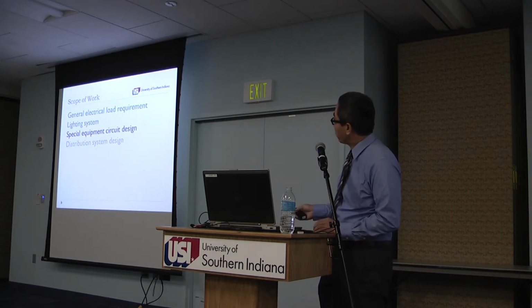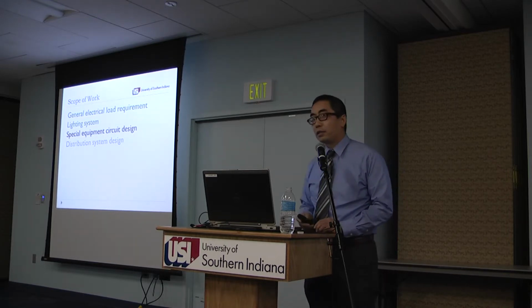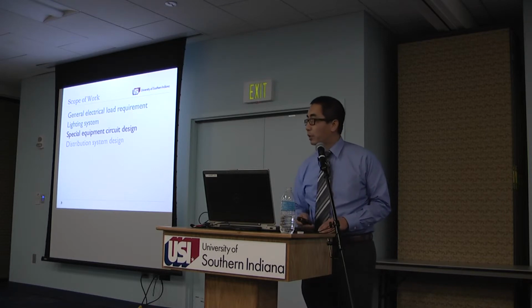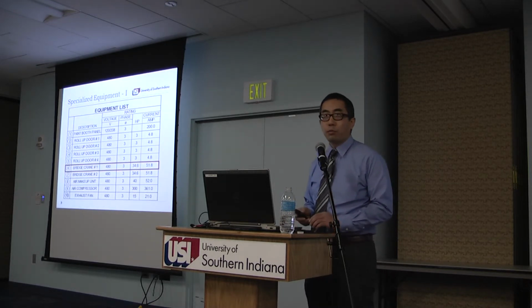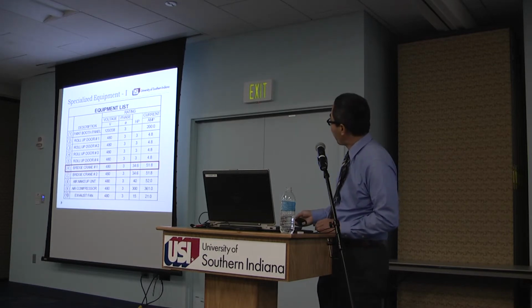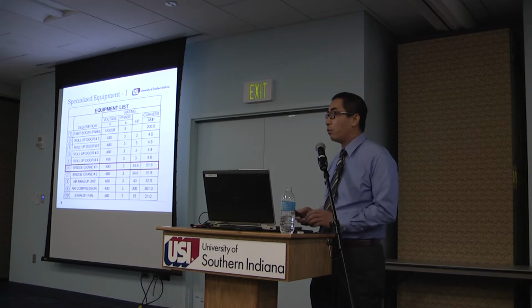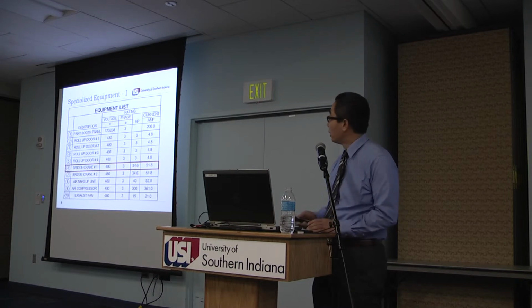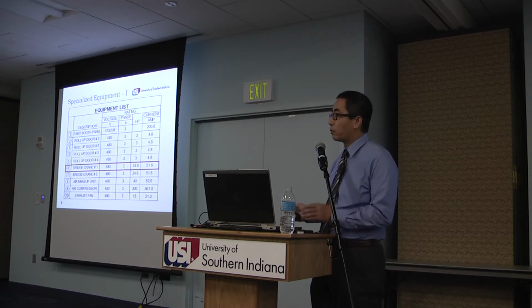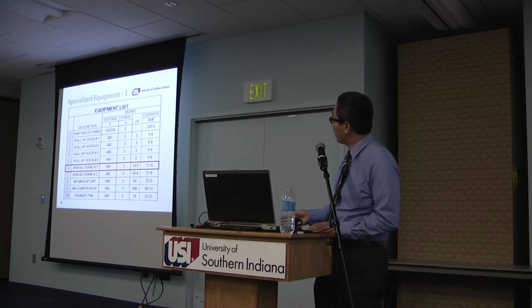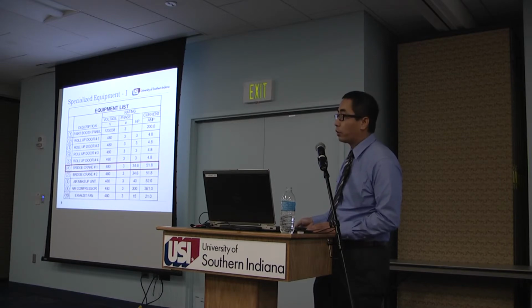So now we're done with the general electrical load and lighting system. The next one will be the special equipment design. This is the preparation and painting shop, basically an industrial application. There's a lot of special equipment inside the building we need to supply power to. There's the paint booth. We'll buy the paint booth from a vendor. It will come as a self-contained unit, but we need to supply the power. So we just assume we're going to have a single panel to supply power to this paint booth. Then there are the roll-up doors, the bridge crane, and the compressor on the outside. We use a lot of pneumatic tools, so we need an air compressor. We also have an exhaust fan for the large paint area.